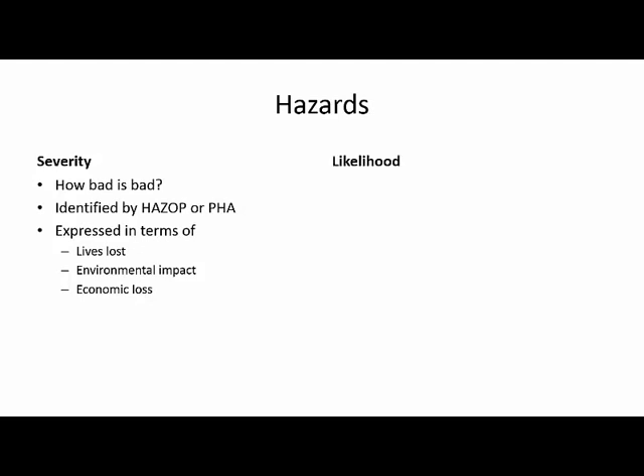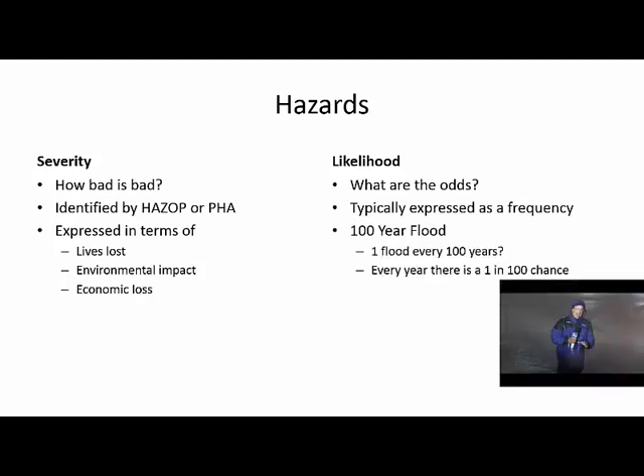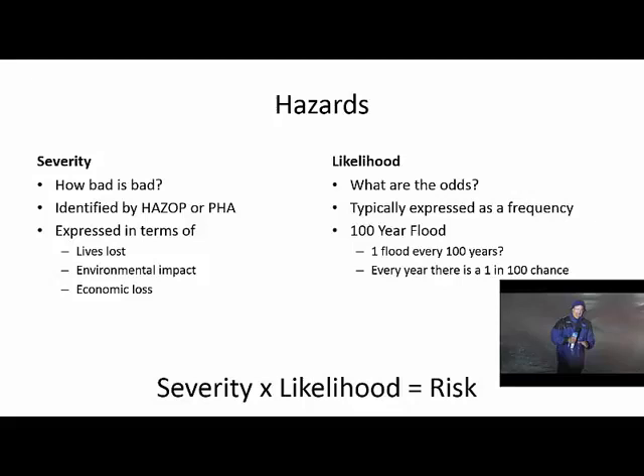The other part is how likely is it to happen. The likelihood is expressed in terms of frequency. For example, something occurs every hundred years. You've all seen the reporter standing in the rain on the hundred year flood, wondering why the hundred year flood happened ten years ago. What's important to know is a hundred year flood doesn't mean it's going to happen every hundred years like clockwork. It means that every year there's a one in a hundred chance of it happening. The same holds true for safety and mean time to failure. So if you take how bad something is and how likely it is to happen, that's your risk. The worse it is, the more risk you're at. The more often it happens, the more risk you're at. That's what plants are trying to manage.